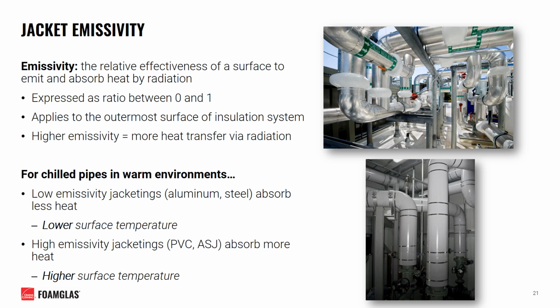When considering chilled water pipes in warm environments, low emissivity jacketing materials, such as aluminum and steel, will absorb less heat from their surroundings via radiation, which will result in a lower jacketing surface temperature. Conversely, high emissivity jacketing materials, such as PVC and ASJ, will absorb more heat from their surroundings, yielding an overall higher surface temperature for the same system.